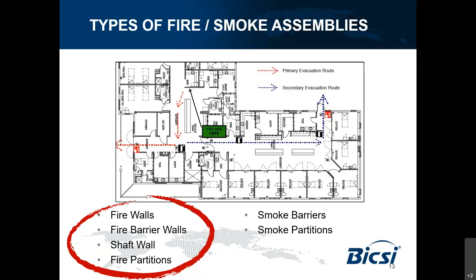Smoke wall is also quite confusing. Currently in the Australian building code, the smoke requirement is not very clear. I've heard many times in hospital projects or certain projects they request a smoke wall, but smoke wall is not a very clearly defined wall type, unless they talk about smoke barrier. Smoke barrier is relatively well defined — it means the wall needs to be fire rated and also smoke sealed, taking on both requirements. But smoke wall, from what I know, is currently unclear in the Australian market. Normally, people see a smoke wall as only requiring smoke seal, not really fire rated.